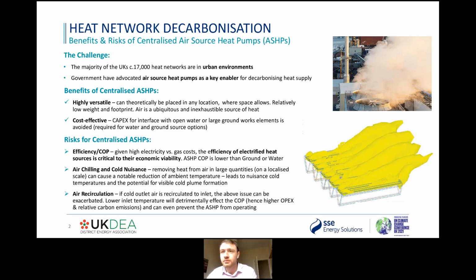We've shown a snippet from the CFD model, which I'll go into in a bit more detail. On the right there in yellow is a cold plume extending from the V banks of an air source heat pump array. The other issue with this air chilling is that the heat pumps cool the air and then recirculate it as they draw it in to feed the next round of heating. You get a recirculation effect where the cold outlet is fed to the inlet, and it continues and continues, giving an accumulating snowball effect on the local air temperature as the heat pumps continually cool.